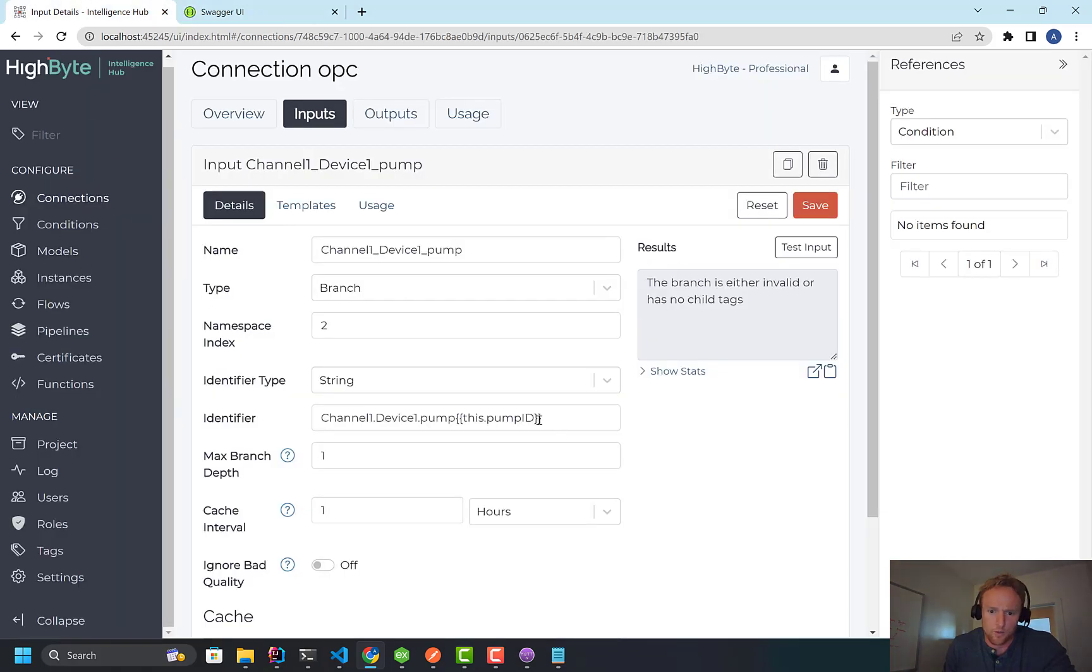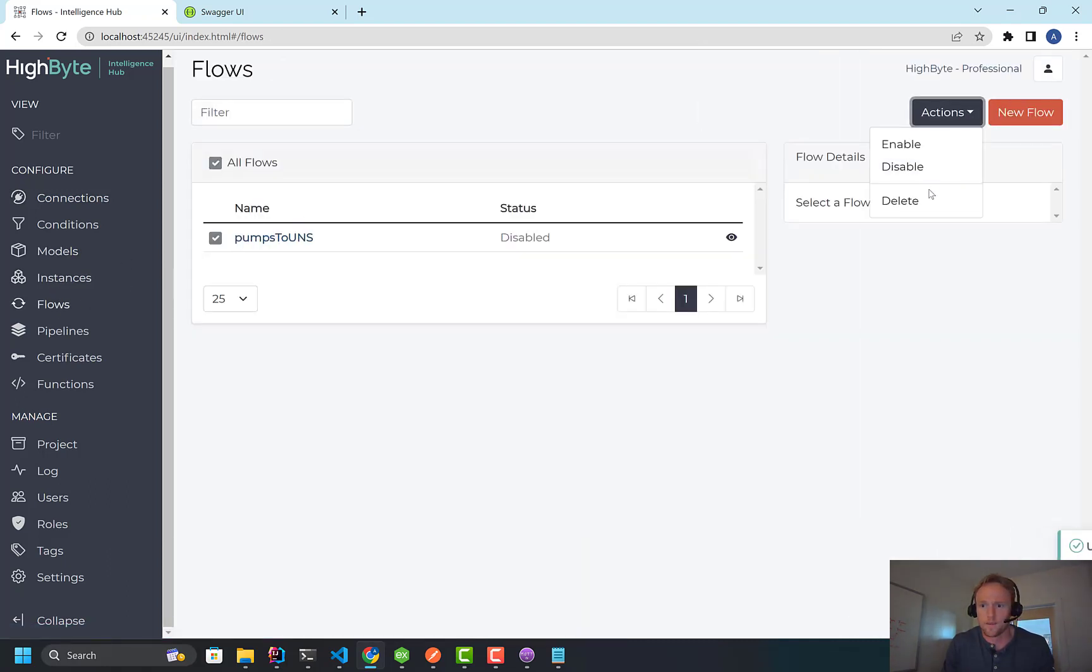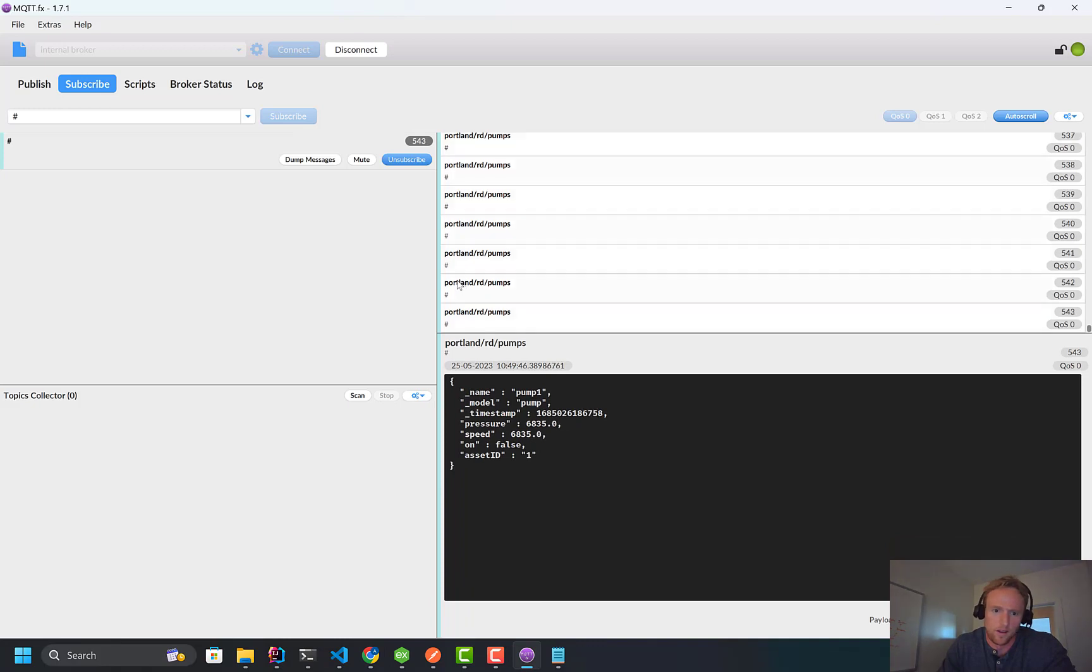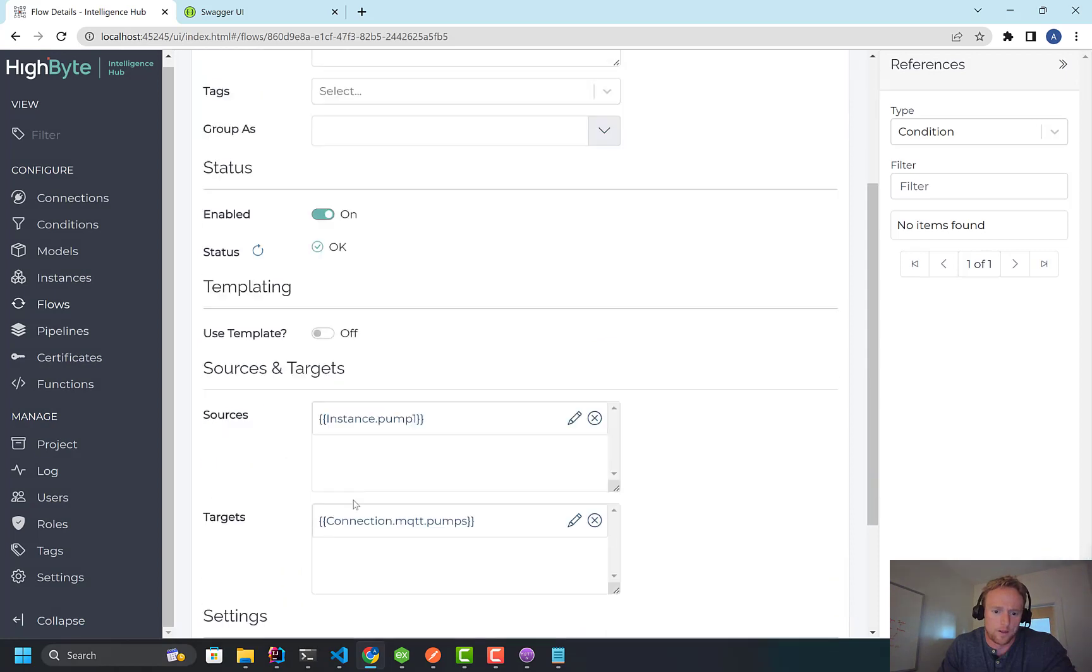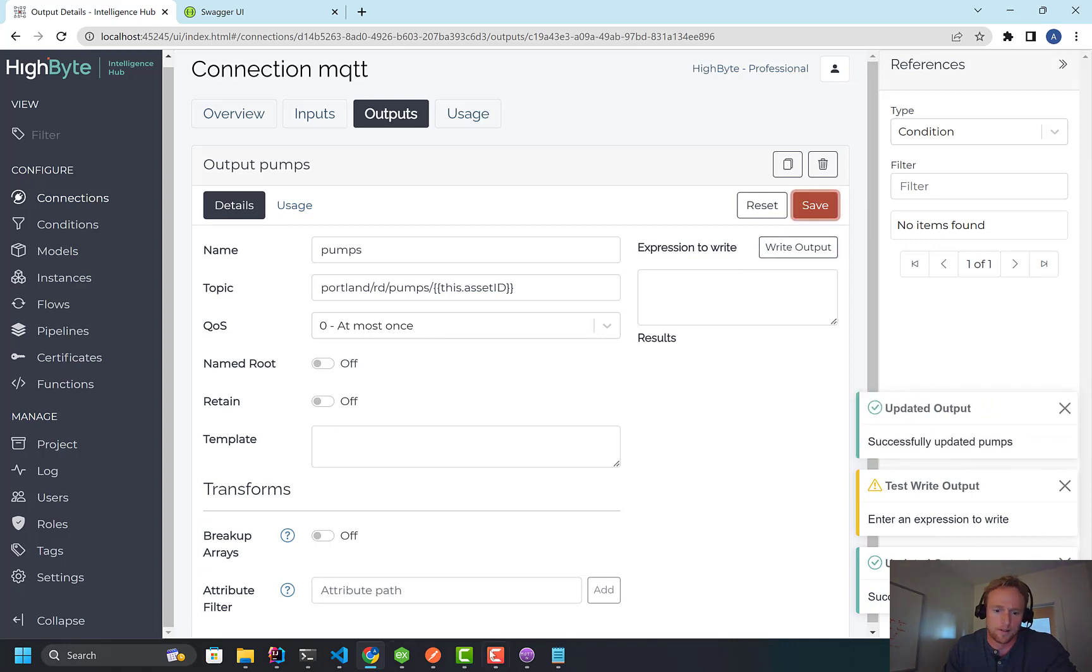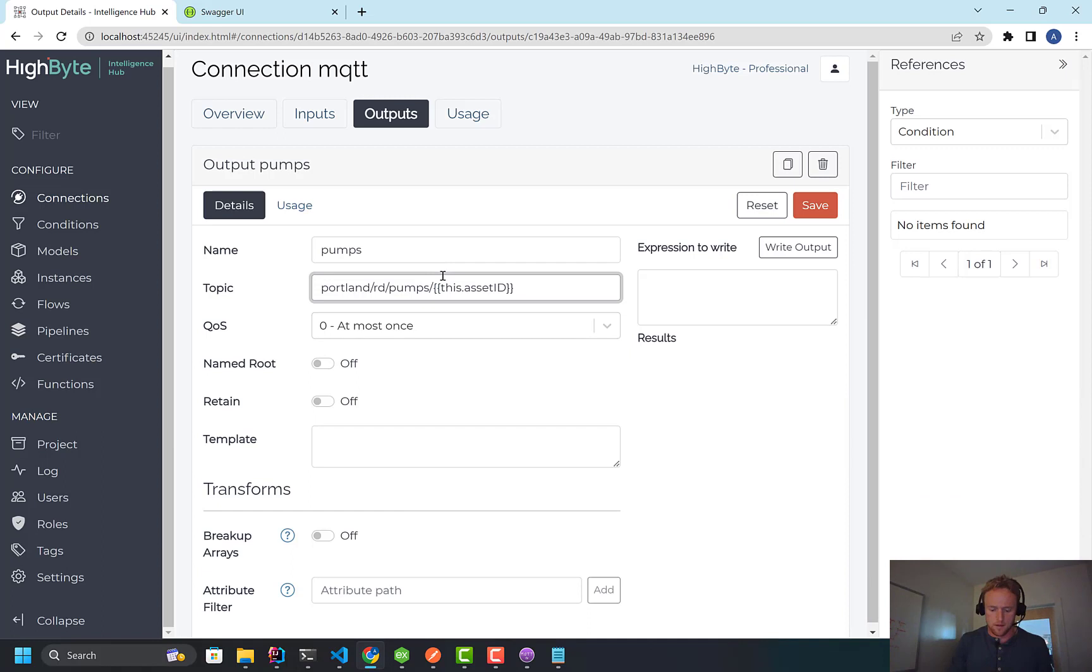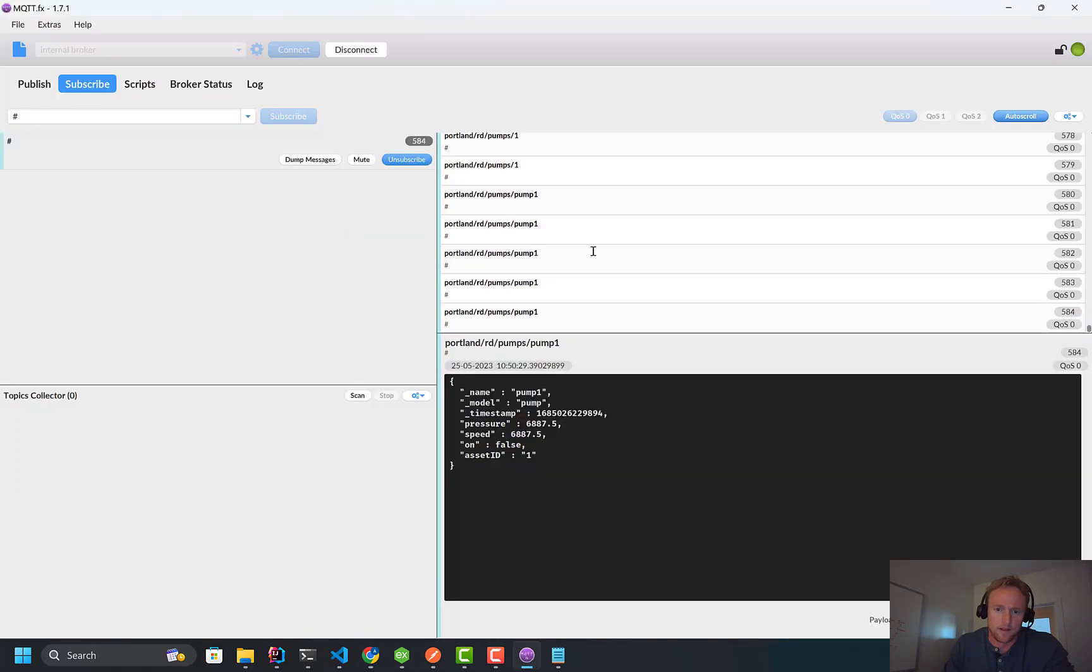So let me, so one more thing on kind of where we're taking this and let me just fix this back up and turn the flow back on. And this is really in the concept of UNS. So one thing you'll notice is that in here, when this data starts flowing, this is on Portland R&D pumps and this is all my pump data. And I would probably extend this. I'd probably go in production to this flow and parameterize the output to be like this dot asset ID. So I'm going to take that piece of information from the payload and I'm going to put it, oops, didn't mean to write. I'm going to put it in the topic. So you'll just see that the pump ID comes out here. And actually to make that a little cleaner, I'll probably just put pump in front of it. So I'm starting to build the UNS, right? The namespace part and then the model data comes in, which is cool. So you can kind of see this address, right? In MQTT.